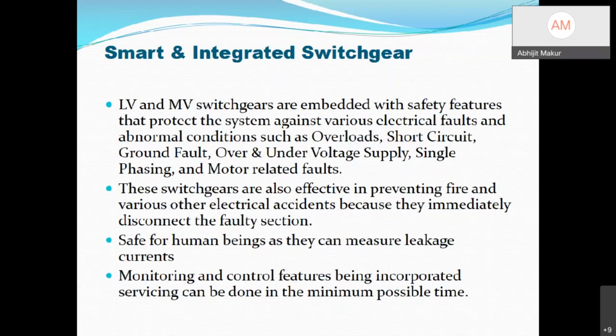Low voltage and medium voltage switchgears are embedded with safety features that protect the system from various circuit overloads, short circuits, ground faults, under voltage, single phasing, and motor related faults. These switchgears are effective in preventing fire and various other electrical accidents because they immediately disconnect the faulty system. They are safe for humans as they measure the leakage current or partial discharge. Monitoring and control features are being incorporated so that it can be done in the minimum possible time. Next.